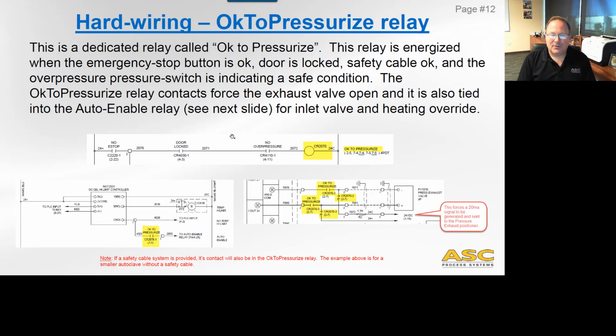So let's look at some examples of OK to pressurize, of hardwired interlocks. You're going to find a certain relay in all of our control systems called the OK to pressurize relay. And this relay coil right here is typically tied to a number of permissive contacts. And when I say permissive, it means those contacts have to be enabled or provide power to permit that relay to energize. And that relay is then used throughout the system to do specific hardwired interlocks. So the OK to pressurize relay is energized when the emergency stop button is OK, the door is locked, the safety cable is OK, and the overpressure switch is indicating a safe condition.